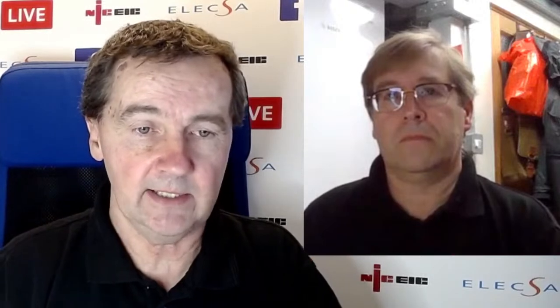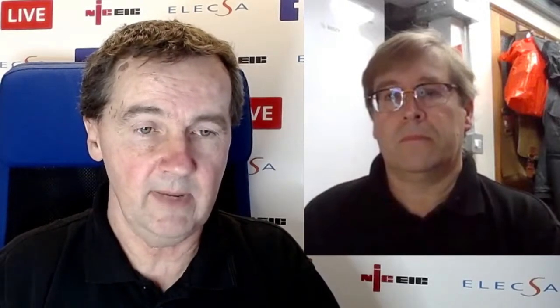And then the only difference with a type C, again on the top of your fraction you have 230 times 0.95, but this time on the bottom of the fraction you've got 6 amp for the rating multiplied by 10, because a type C can take between 5 and 10 to trip. So you can actually calculate those values, and it's a nice logical method that you can use to do it.